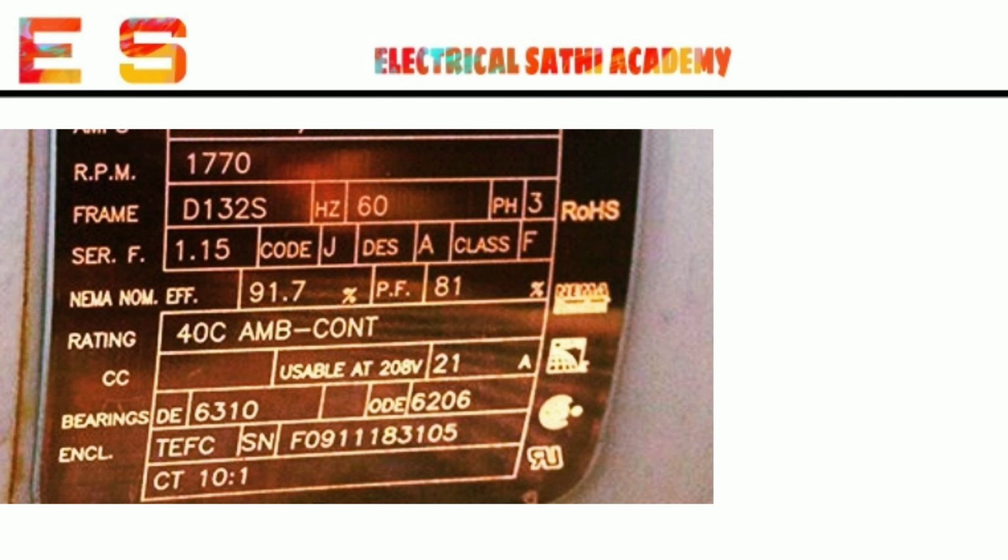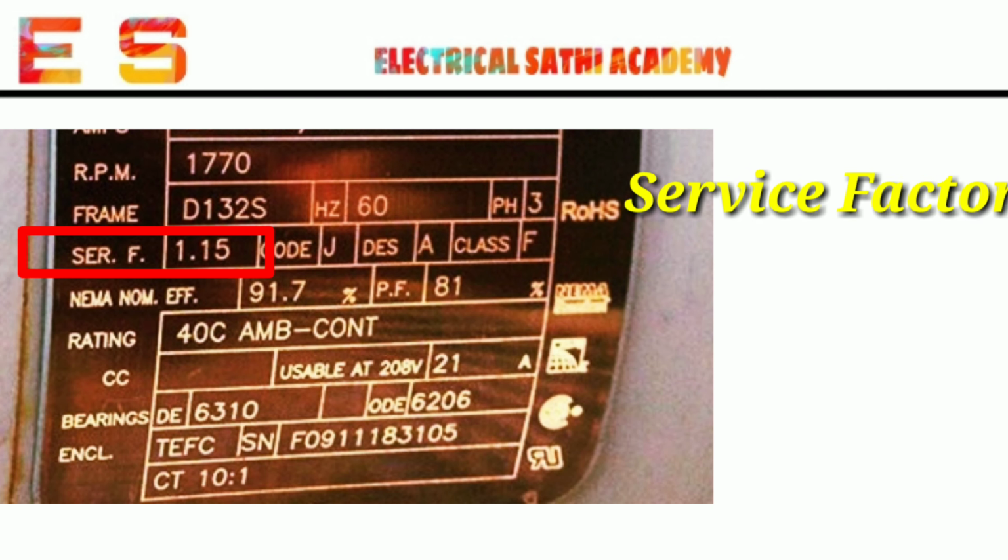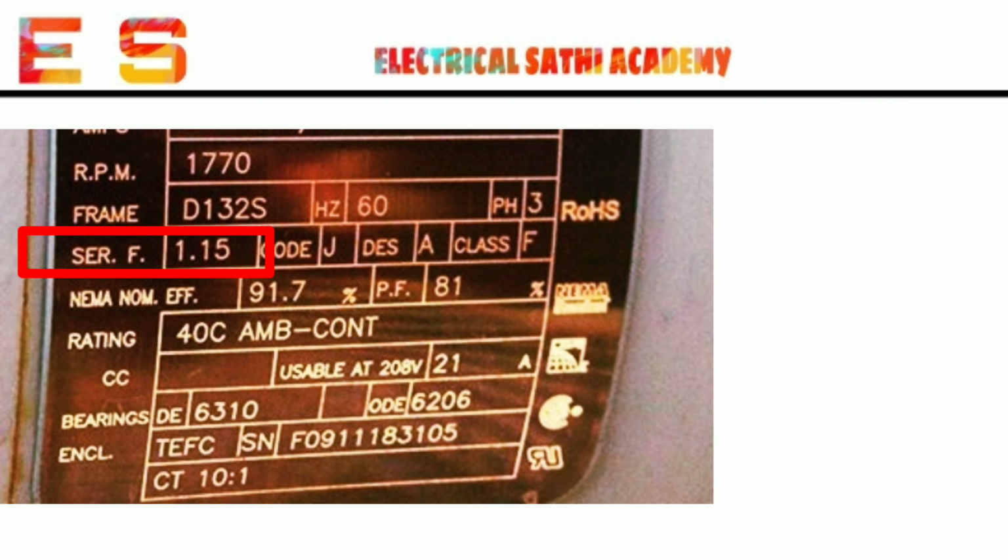Service factor. What it means is that the rated mechanical output of the motor is 7.5 horsepower. It can also drive a load which requires horsepower which is 1.15 times the rated horsepower. But be careful, not more than that.